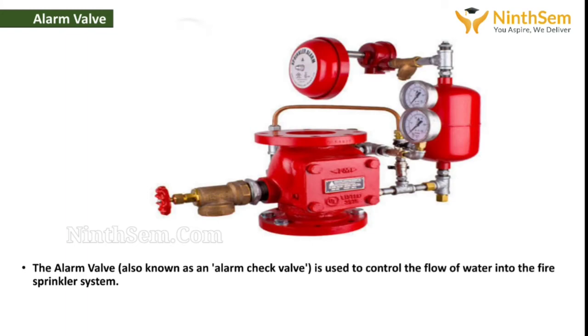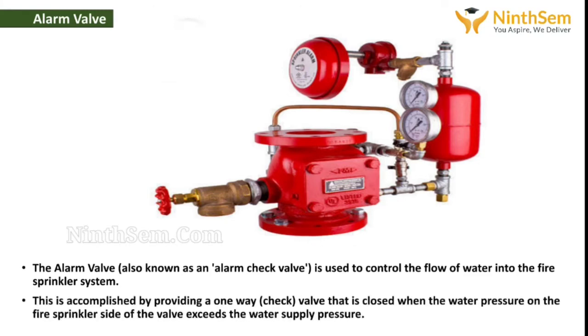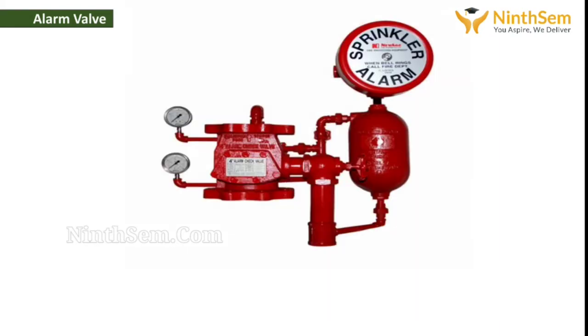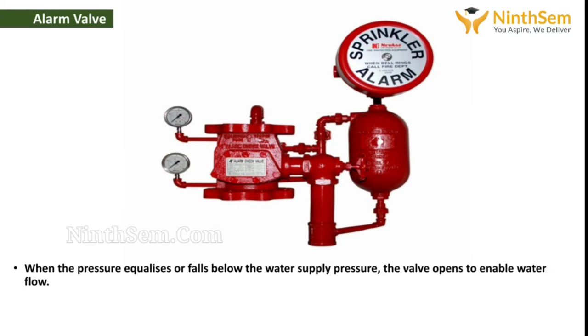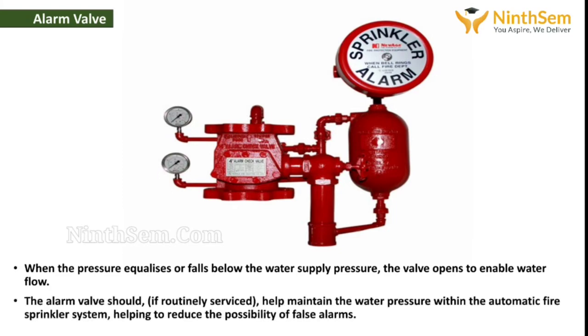Next, the alarm valve. The alarm valve, also known as alarm check valve, is used to control the flow of water into the fire sprinkler system. This is accomplished by providing a one-way check valve that is closed when the water pressure on the fire sprinkler side of the valve exceeds the water supply pressure. When the pressure equalizes or falls below the water supply pressure, the valve opens to enable water flow. The alarm valve should, if routinely serviced, help maintain the water pressure within the automatic fire sprinkler system. And this helps to reduce the possibility of false alarm.